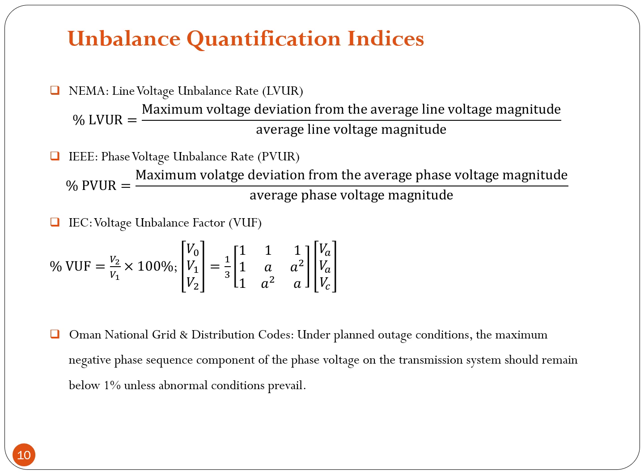This slide presents the unbalance quantification indices. The National Electrical Manufacturers Association (NEMA) used the line voltage unbalance rate to calculate the unbalance as the ratio between the maximum voltage deviation from the average line voltage magnitudes to the average line voltage magnitudes. The Institute of Electrical and Electronics Engineers (IEEE) used the same unbalance description with a slight change, as the IEEE applies phase voltage instead of line-to-line voltages.